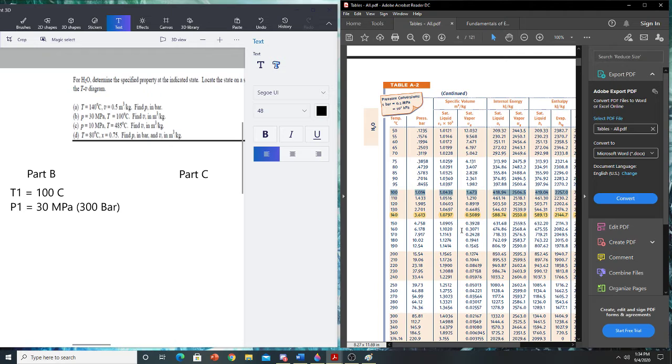Because, remember, for the temperature table, the relationship is inverted. If we are over that number, we are subcooled. We are compressed liquid. But on the pressure table, we are superheated if you're over the number. So that was why this question was the trickiest one: here we are a subcooled liquid because we are over this number. So the relationship flips on the temperature table or the pressure table.